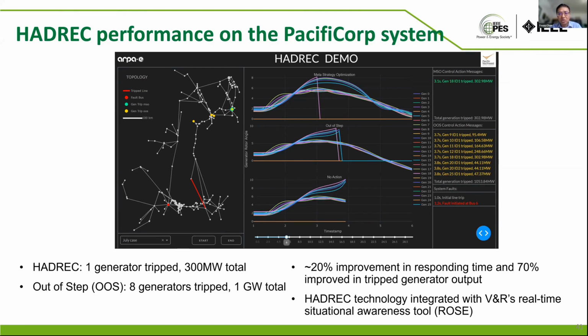In the middle, the top curve is the actual generated local angle curve from our HADREC algorithm, the middle one is the curve if today's out-of-step protection algorithm were used, and the last one shows what happens if no action is taken—apparently the system becomes unstable. On the right side is more information on actual action messages, including the time and which generators are tripped along with their generator capacity, and at the bottom, system fault information including what kind of tripping or events occurred at what time.